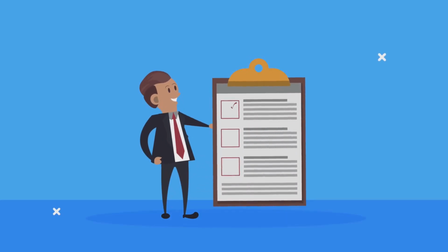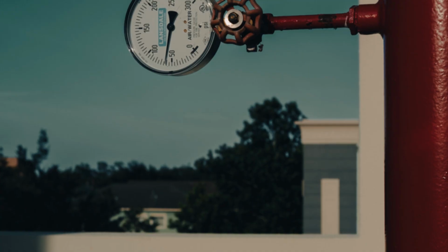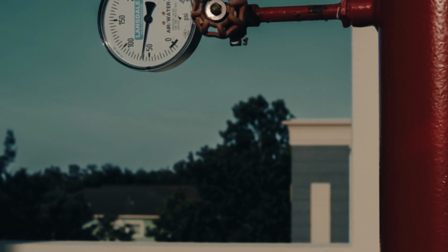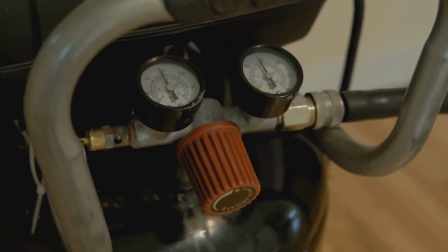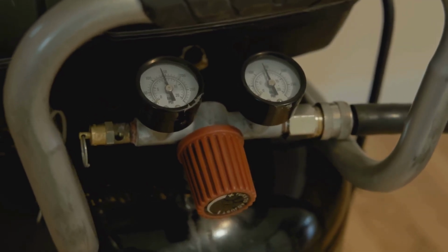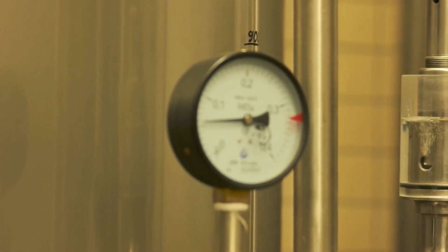A quick mental model to apply. One, pick your target phase change. Two, look up the fluid saturation pressure at your desired temperature. Three, make the system pressure slightly above that to condense, or slightly below to boil or evaporate. Four, add control and safety margin.